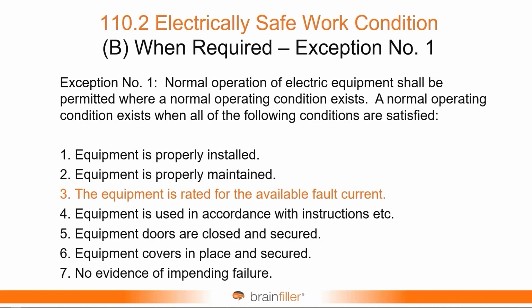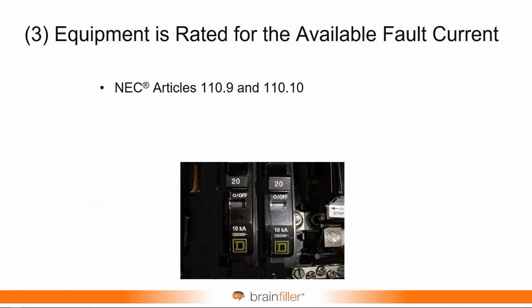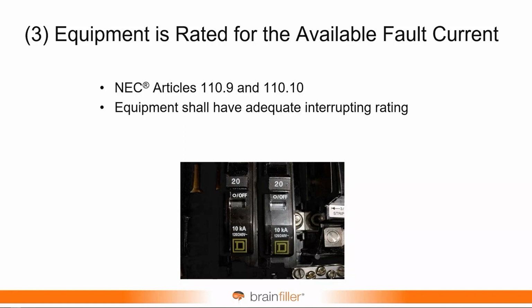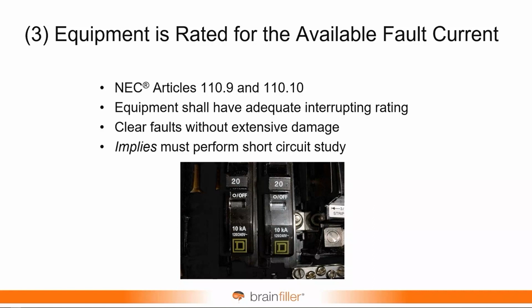And this is part of 110.2, electrically safe work condition, B, when required, exception number 1. The new addition was that the equipment is rated for the available fault current. So, for example, if you have equipment that has a certain interrupting rating, the National Electrical Code requires that the equipment has to have an adequate interrupting rating, and now you see that in NFPA 70E. The National Electrical Code requirement doesn't specifically state that you have to perform a short circuit study, but it kind of implies that you do, to verify that the equipment has an adequate interrupting rating. So carrying this over to the conditions, we have a 7th condition now.